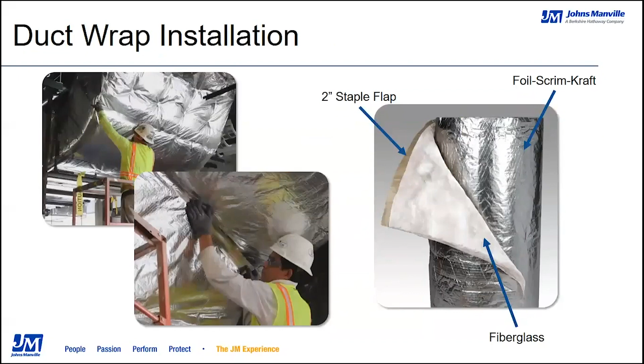It's always important to make sure that you put the foil facing, or your FSK facing, toward the outside. You want to tightly butt your seams together, and then that 2-inch staple flap must completely overlap that facing as you wrap it around the duct, and you want to make sure it all comes together. Rectangular and square ducts are to be installed so that the insulation is not excessively compressed, especially at the corners, and those seams should all be stapled approximately 6 inches on center with an outward clenching staple, which is very important. You need to make sure that you seal all the seams and joints with a pressure-sensitive tape that matches the facing, either glass fabric or mastic as well. Those are some of the basics for installation of duct wrap.